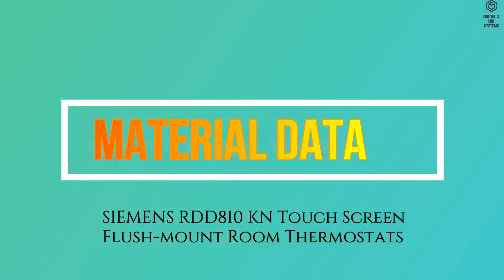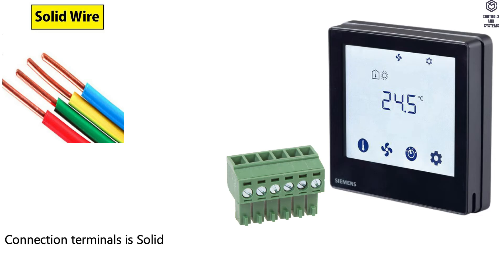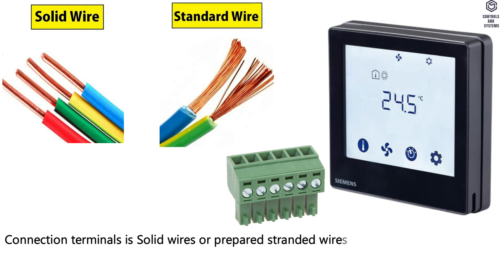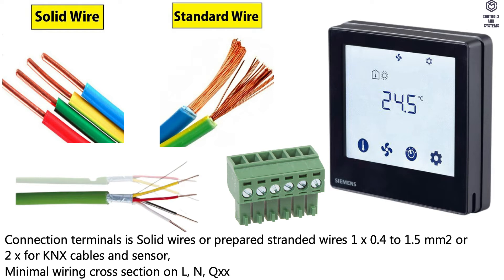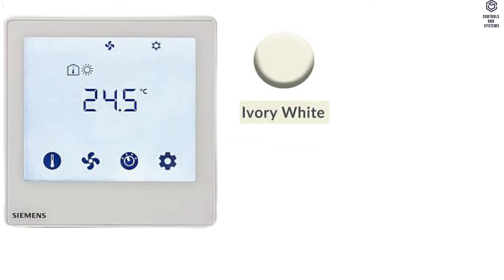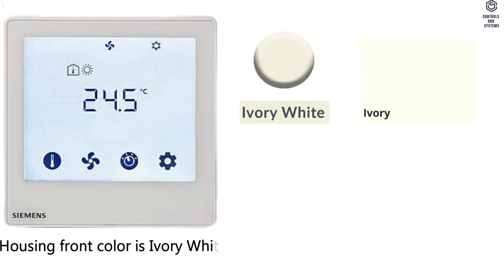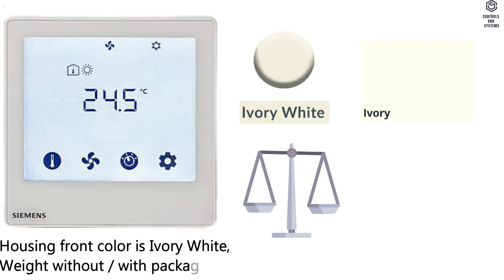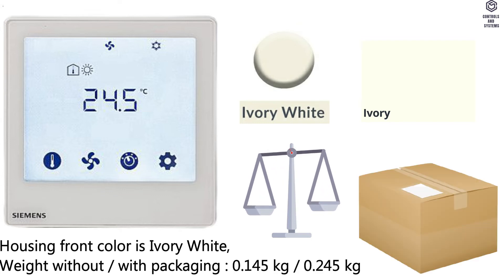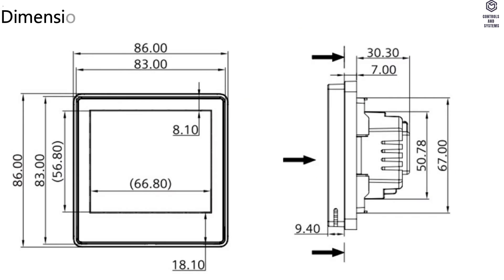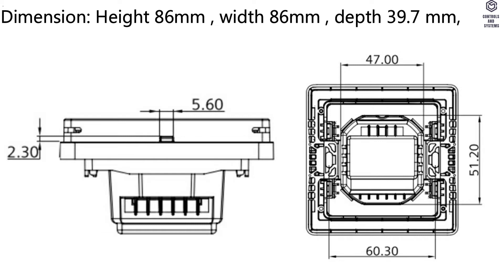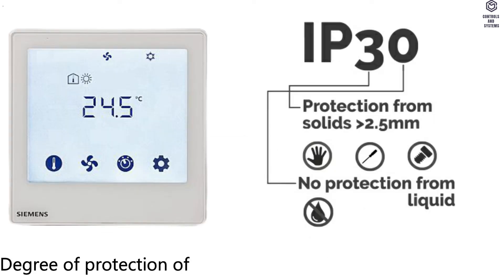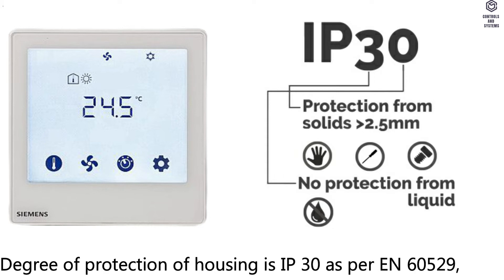Material Data: connection terminal accepts solid wires or prepared stranded wires, 1 × 0.4 to 1.5 mm² or 2× for KNX cables and sensor. Minimal wiring cross-section on L, N, QXX is minimum 1.5 mm². Housing front color is ivory white. Weight without packaging: 0.145 kg; with packaging: 0.245 kg. Dimensions: height 86 mm, width 86 mm, depth 39.7 mm. Degree of protection of housing: IP30 as per IEC 60529.